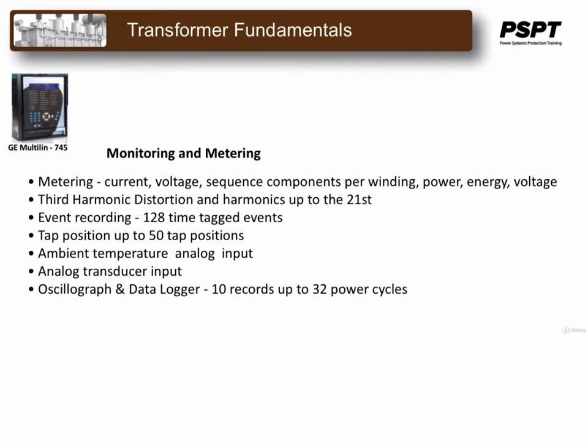Along with the protection and control features, this package also includes metering of current, voltage, sequence components per winding, power, and energy. It also tracks third harmonic distortion and the other harmonics up to the 21st. It is also an events recorder. It will also track the tap positions of an on-load tap changer transformer up to 50 tap positions. It will also record the ambient temperature using an analog input, and it also has analog transducer inputs for other functions. It also has a built-in oscillograph and data logger to track any events that need to be looked at after the fact.